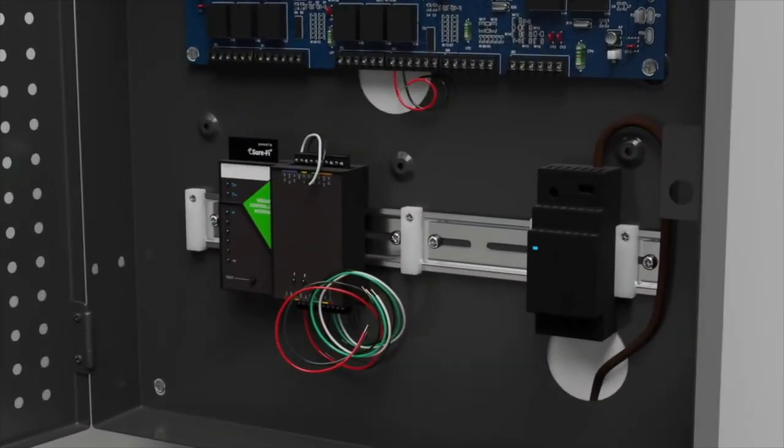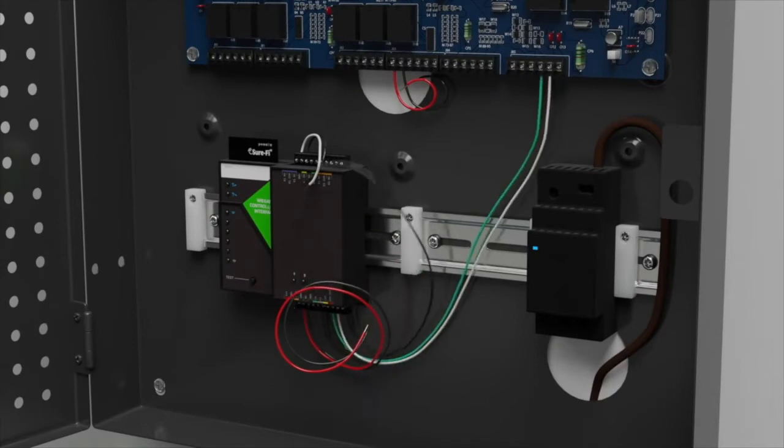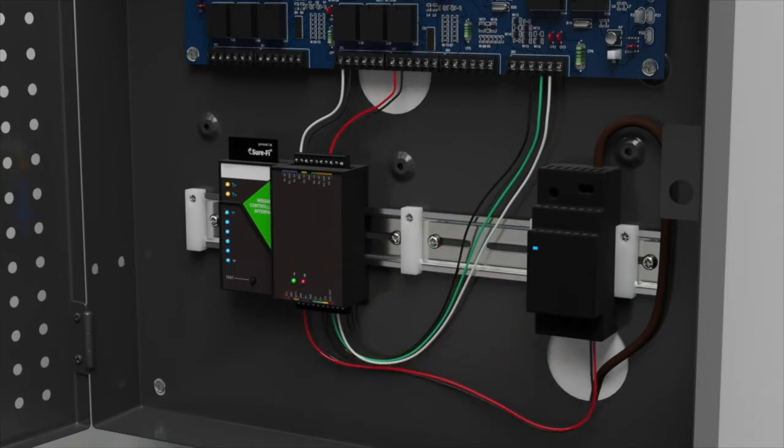On the controller interface, connect the Wiegand D0, D1, and ground on the bottom of the SureFi to the Wiegand inputs on your control panel. Connect the relay outputs from the panel to the relay inputs R1, N, or R2, N, and ground on the top of the SureFi controller interface. Connect 12 volts DC power.